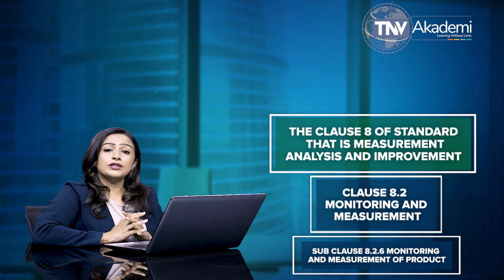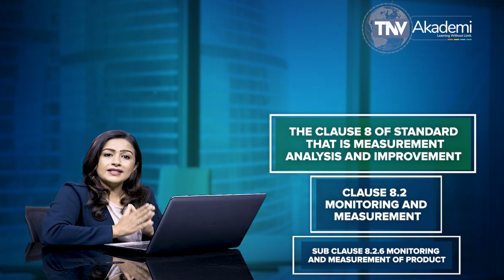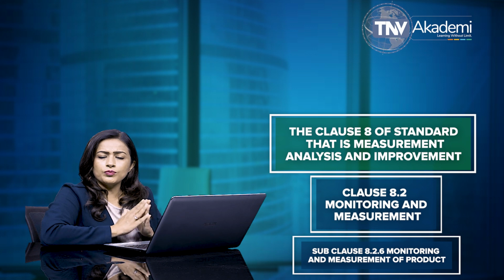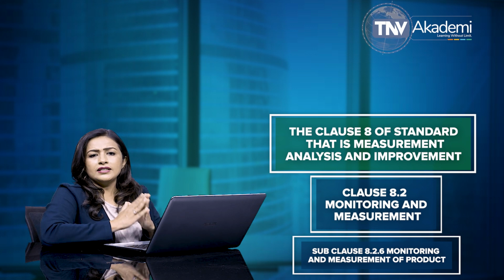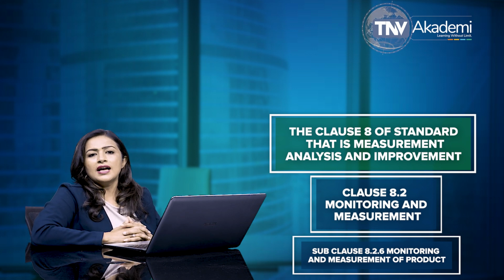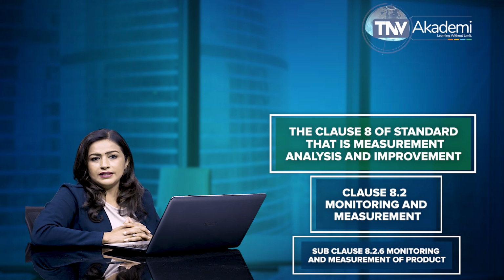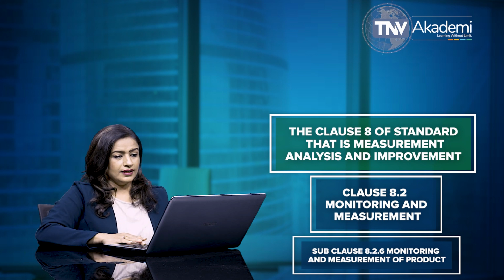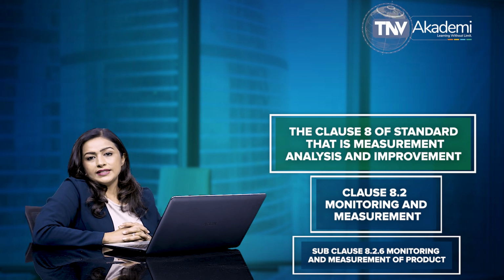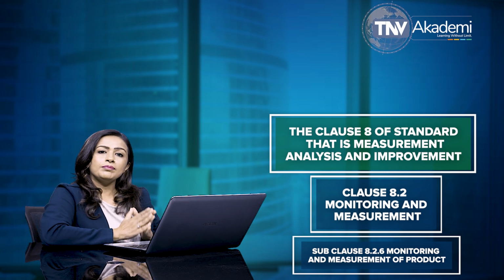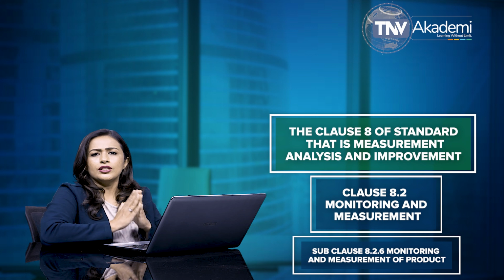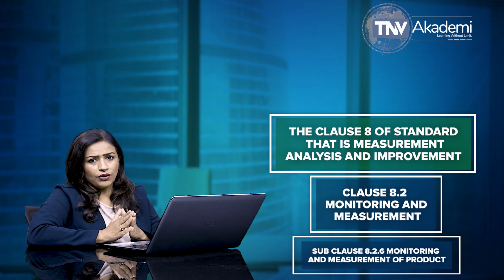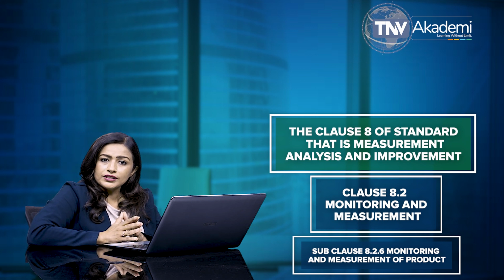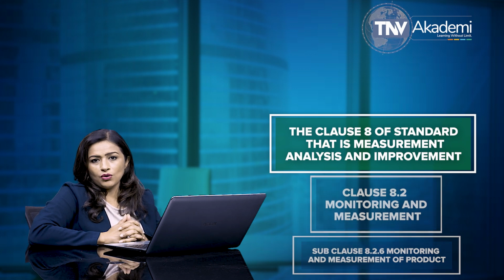Further, as per this standard, the product release and service delivery must not proceed until the planned and documented arrangements have been satisfactorily completed. The subclause 8.2.6 states that for implantable medical devices, the organization is required to record the identity of personnel performing any inspection or testing.